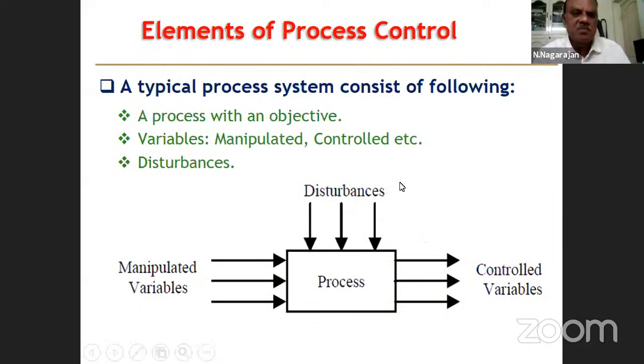So we just see a block flow diagram of how this whole process system is operating. The process has some objectives. What we have seen already means it has to handle so much capacity. It operates within certain pressure and temperature conditions. And now we have variables which are manipulated and controlled, which in the previous slide, the controlled variable is your head. Disturbance means there may be external disturbances acting on the system, like atmospheric conditions. It has more effect on equipment like cooling towers. Rain or very hot weather will have an effect on the cooling tower performance because it affects the humidity. So with the manipulated variables and disturbances which get into the process, and the controls in place, what we get is the controlled variables.